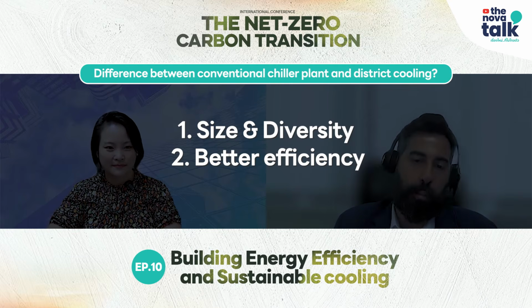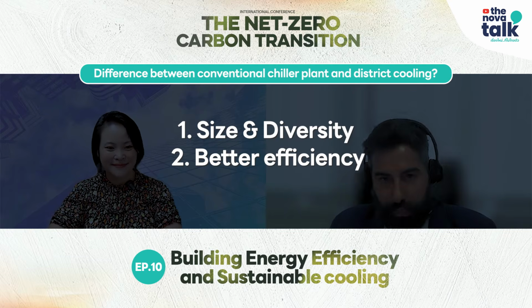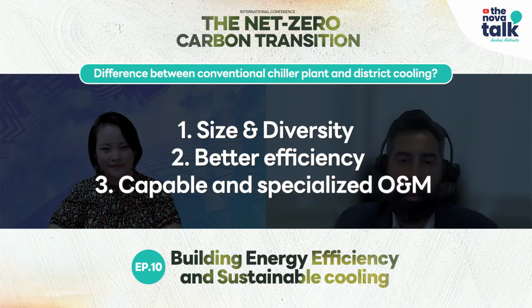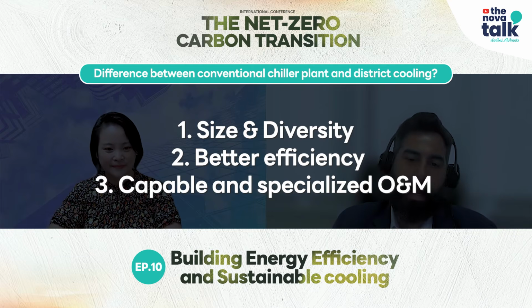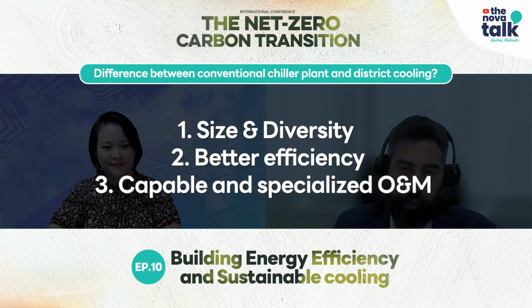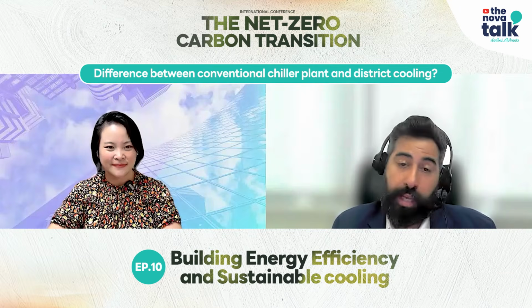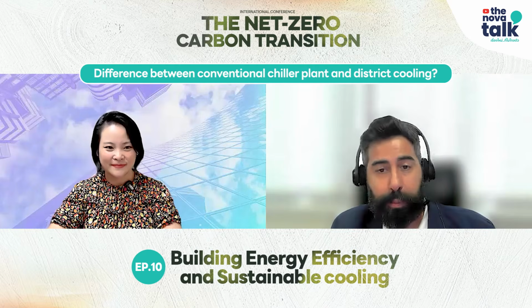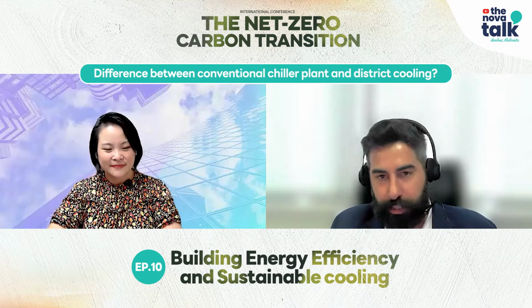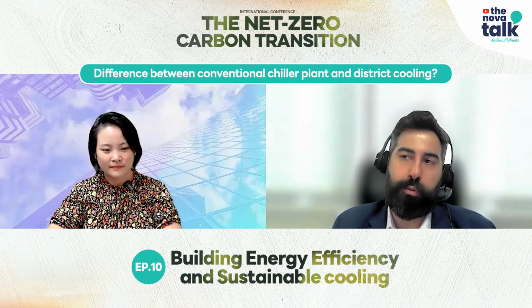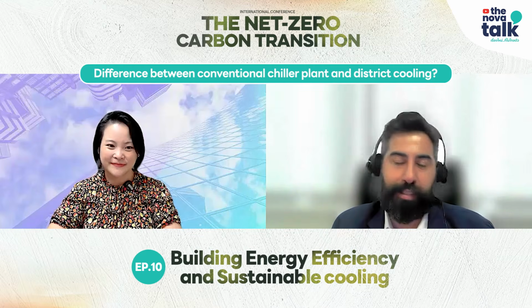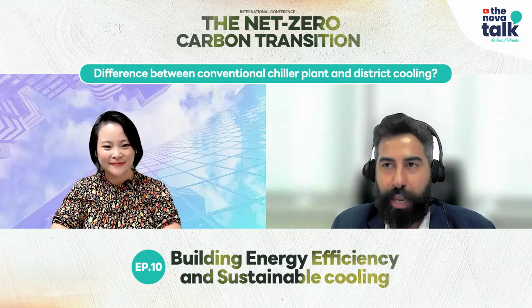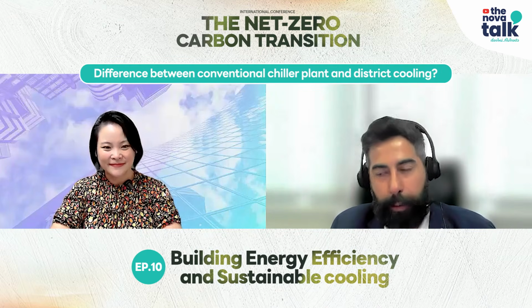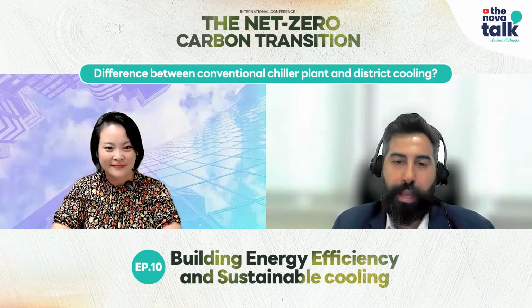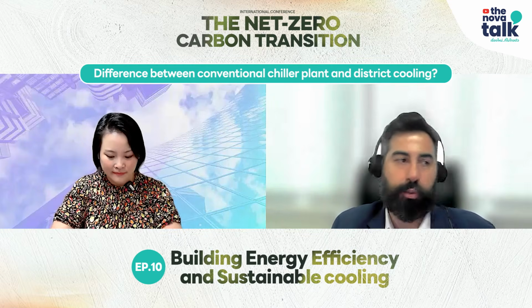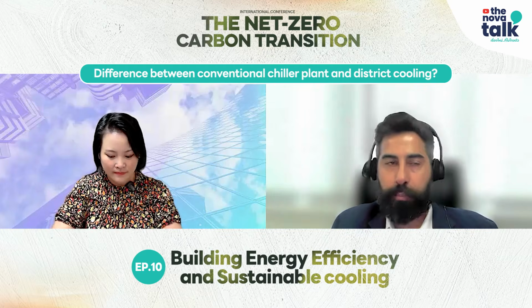The design will be better, and the operation and maintenance - since you have a capable district cooling provider with specialized teams - they run that plant more efficiently than those 20 would. Out of those 20, maybe 2 have really good facility management companies running their plants well, but probably not the other 18. With a central district cooling plant, 90% or 99% of the time you have a capable team because they are selling that chill water - they want to produce it at the lowest cost possible. That's the incentive they have, compared to chill water produced locally.